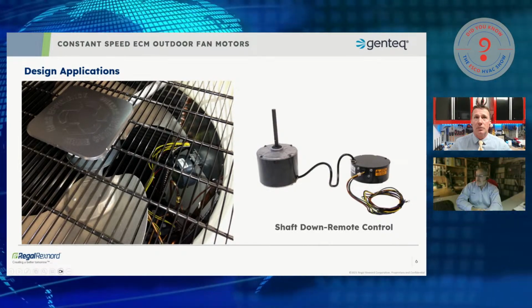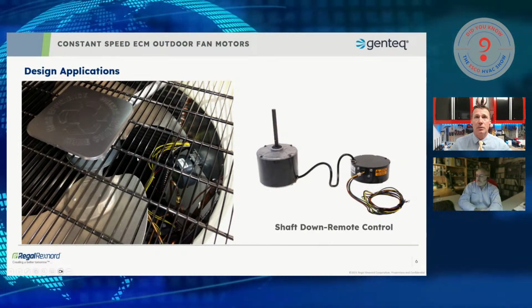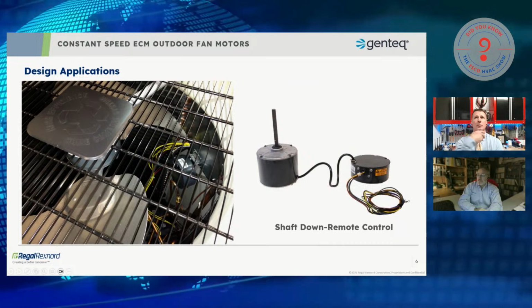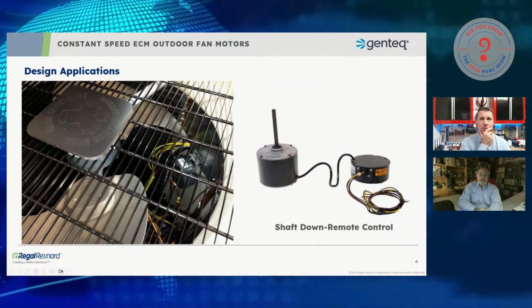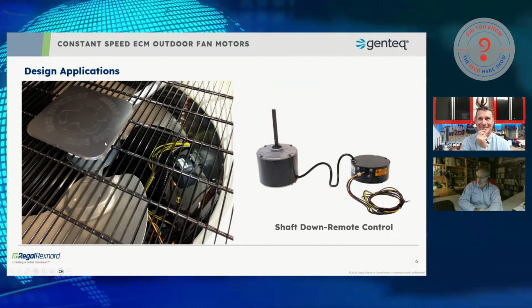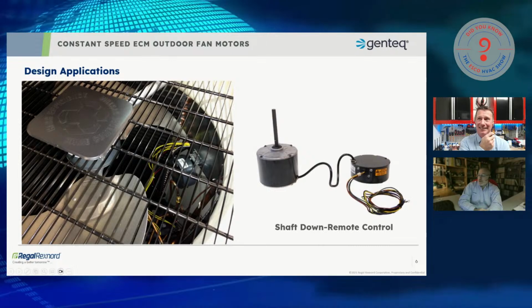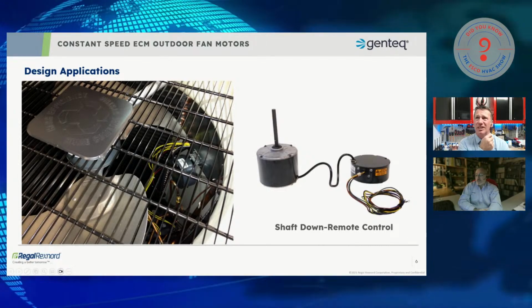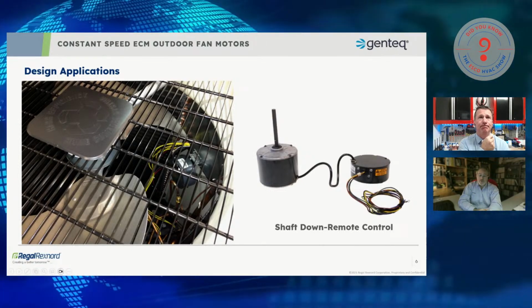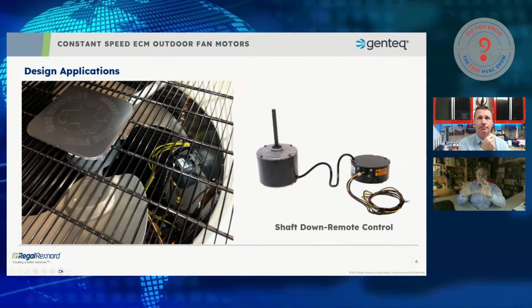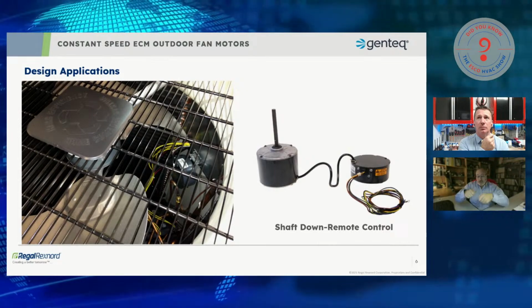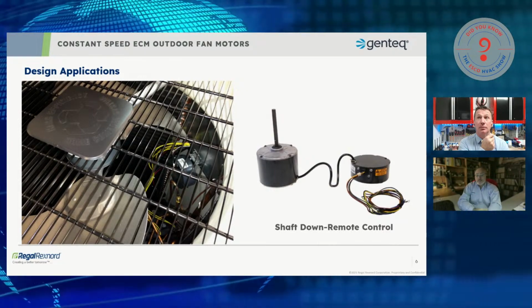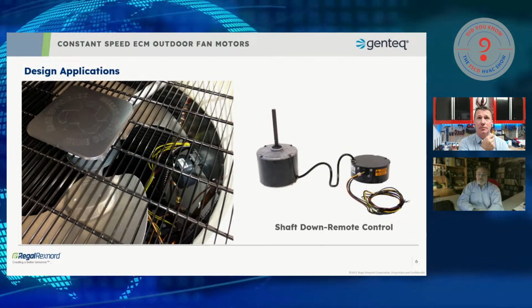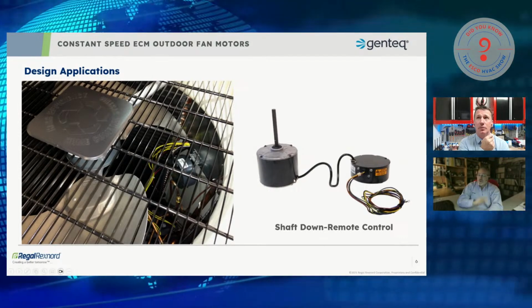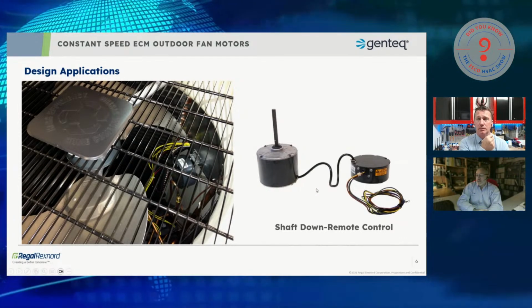What's funny about this configuration is if the technician isn't paying attention, they may simply think that that's a PSC motor, because it looks like a PSC motor. There's no electronic control on the back of it. And if you don't follow those wires down and see that controller, if you take the panel off and just start, I've got 230, it should be running, you'll miss the fact that this is an ECM and it operates a little differently. So it's worth looking inside and looking for those added components.